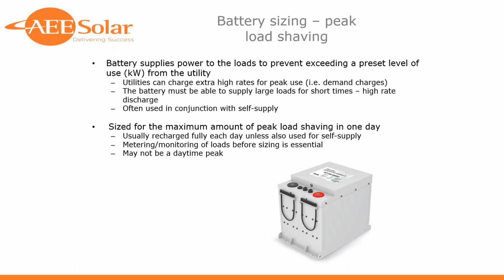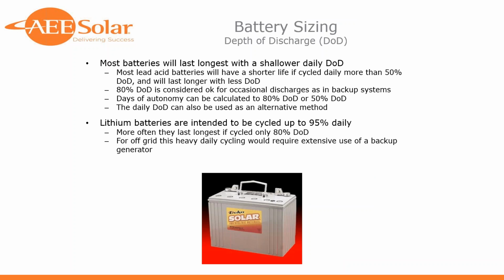So I think this is a great segue to our next slide, Brad, where we talk about trade-offs between amp hours and depth of discharge, and how do you think about both when we go through the sizing exercise? Right. Well, there's more into the details of choosing a battery and sizing it. Certainly, some batteries are more amenable to being discharged their whole capacity. Other batteries are not. You may be familiar with all the lead acid type batteries, whether they're sealed or flooded or whatever, really don't like to be discharged their whole capacity. They last much longer if they're only discharged half as much, and actually will last quite a bit longer if they're discharged even less than that.